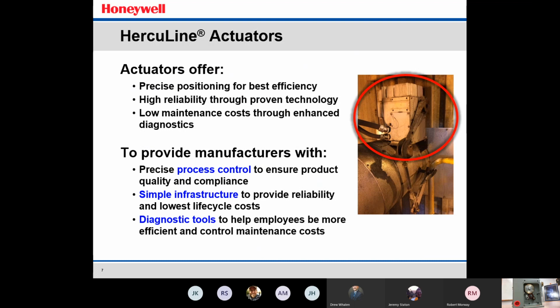As we discussed, the 10260, or actually the whole Herculine actuator family, has very precise positioning to provide best efficiency for your process control. The 10260 actuator, if you're using it in a linear fashion with a 4 to 20 milliamp, has about 1,000 repositions. So when I say 1,000 repositions, that means if you were to take a 4 to 20 milliamp signal, which is 16 milliamps, and divide that up between the 1,000 repositions, that'll show you how precise of a control or a finite control.